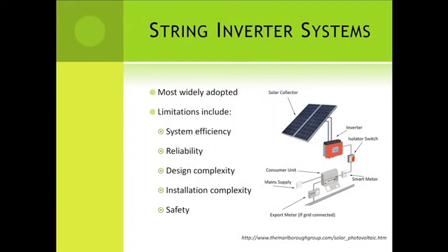Reliability and design complexity: you need to design your system with the exact number of panels in order to withstand the voltage and ampacity of your inverter and distribution panel. Beyond that, installation complexity means you need to design your mounting system right up front, so later on if you want to add 2 or 3 more panels, you have to redesign the entire mounting system.